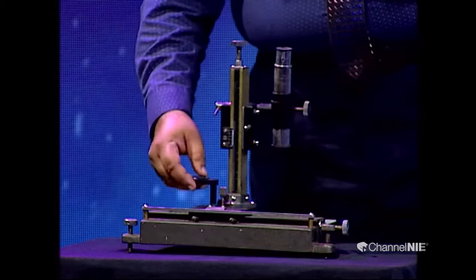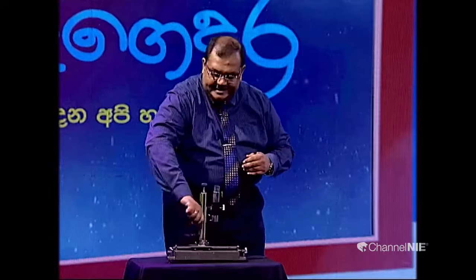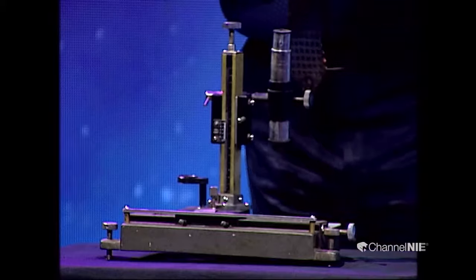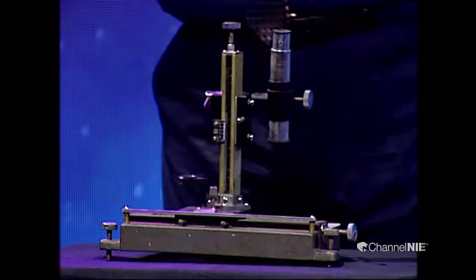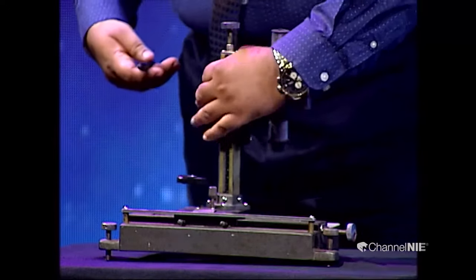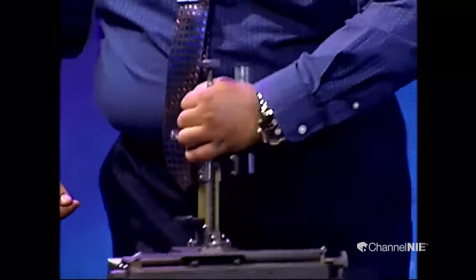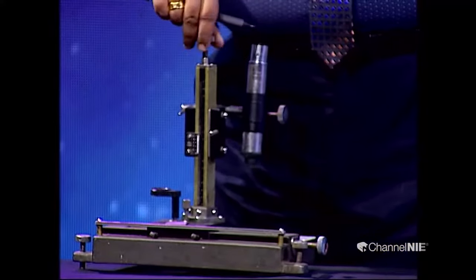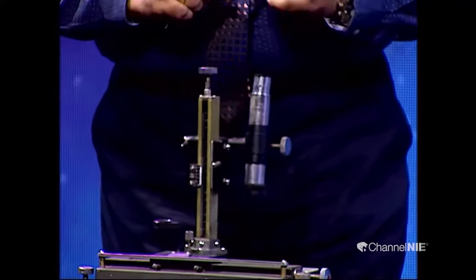And this is the magnifying glass of the horizontal vernier. This is the locking screw of the horizontal vernier. When it is tightened, this fine adjusting screw works. And this is the vertical vernier here. There's a locking screw. Actually, it is located in the back side of this. This is the locking screw of the vertical vernier. When it's locked, this works. Then this is the fine adjusting screw of the vertical vernier.